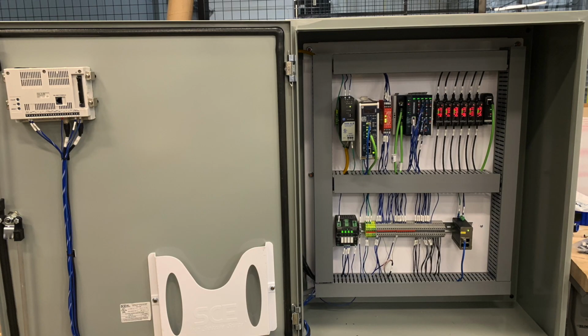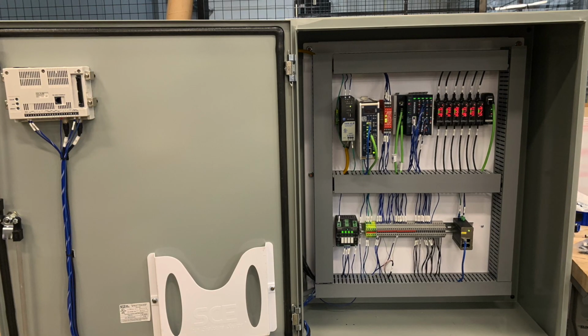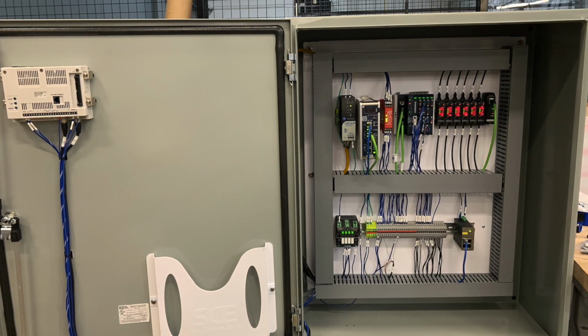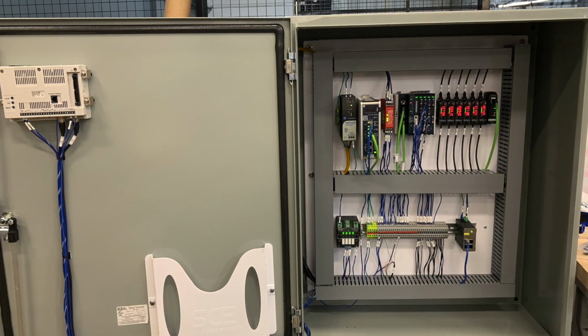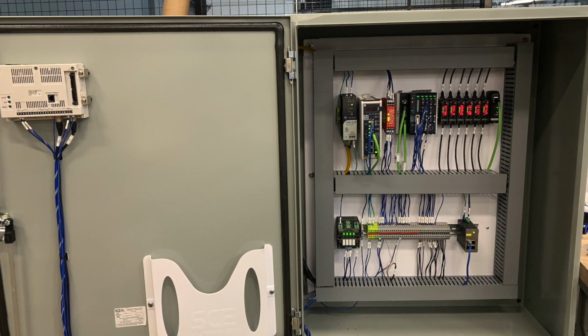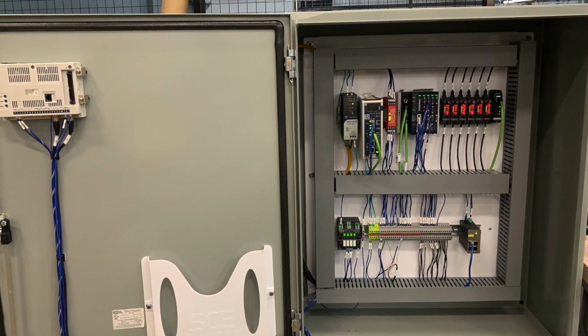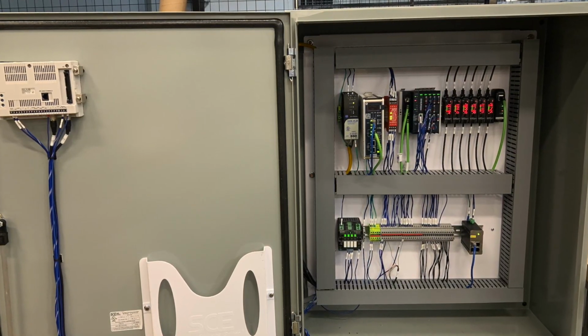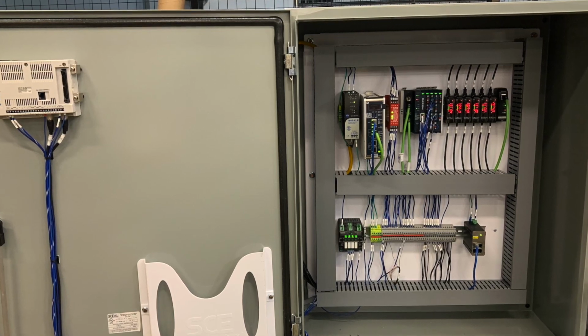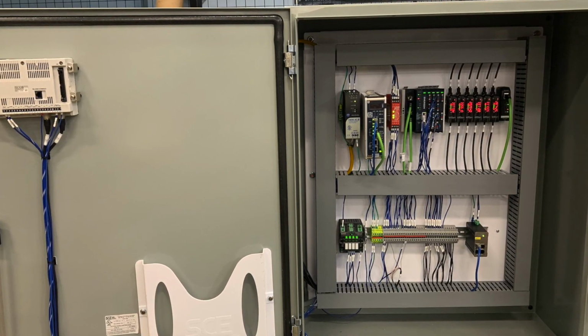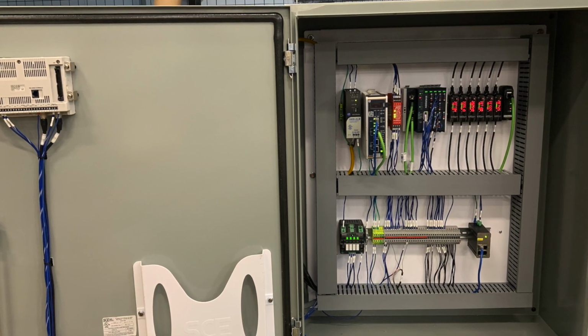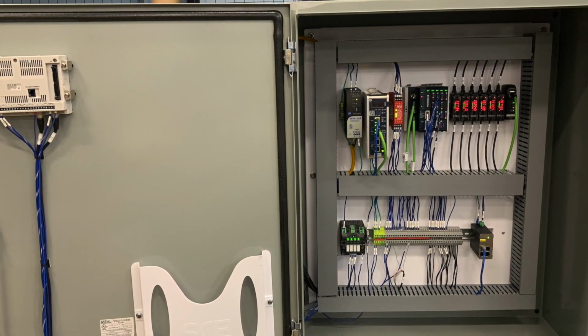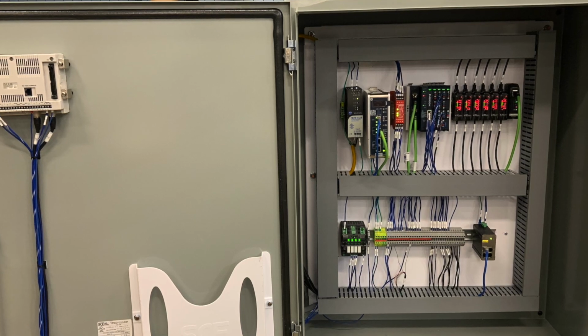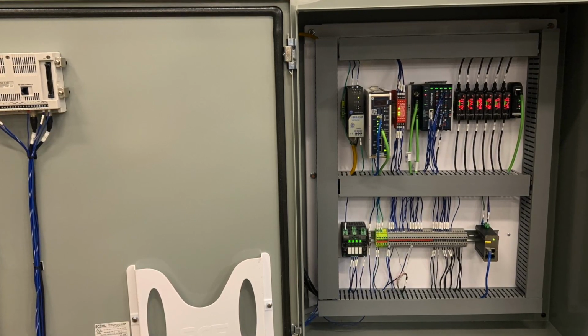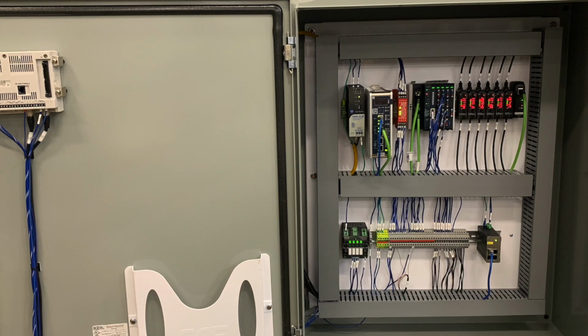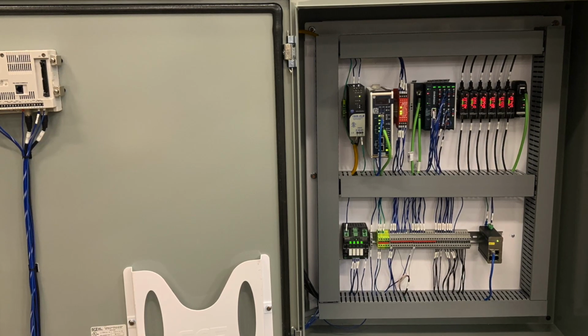To the right of the safety relay is the point I/O and the LVDT amplifiers. The point I/O is responsible for the sending and receiving of discrete and analog signals. Some of these signals include the length measurement from the encoder and the output signal to the pneumatic valve, to name a few. The LVDT amplifiers power and receive data from the LVDTs. A communication module sends this data to the PLC via Profinet, so there is no quantization error from the point I/O's ADC.